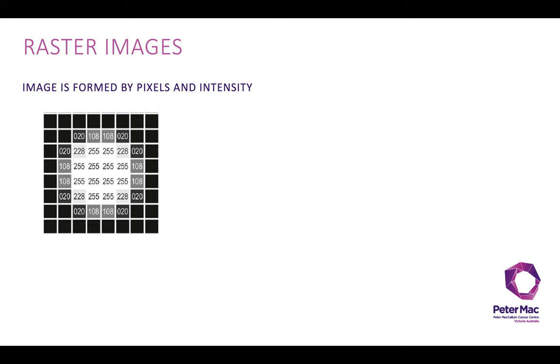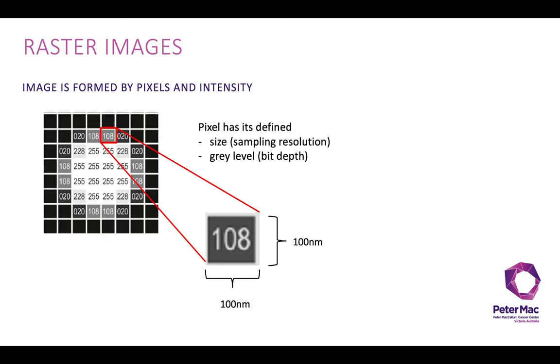Let's start off with the digital image. A digital image, when we're taking it on a microscope, is what we call a raster image. This image is formed by pixels, and each of those pixels has an intensity but also a physical size characteristic. The size is dependent on our sampling, so we can actually set the pixel size and also the intensity scale — what we call our gray level or our dynamic range — which is controlled by something called bit depth. We'll cover both bit depth and sampling resolution over the next few slides.